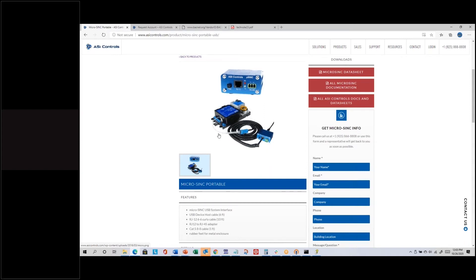You can plug directly into the wall sensor jack of an ASIC/1 to do the initial setup — setting the protocol (BACnet or ASI protocol) as well as other communication settings — so that when installed in the field, they can power up and start talking without interfering with each other. There's a Find button — a spring-loaded button — that shorts Input 3 through the RJ12 cable, allowing you to short the input without having direct physical access to the controller, just wall sensor access.